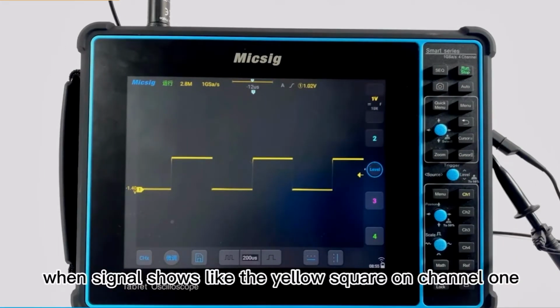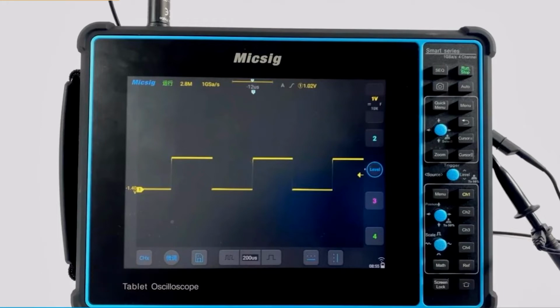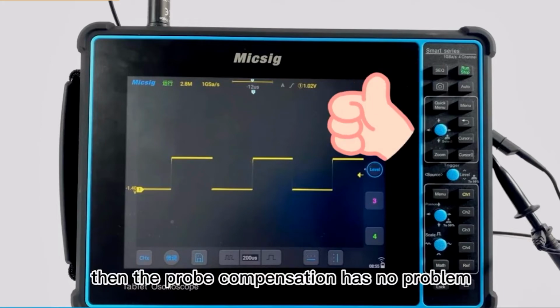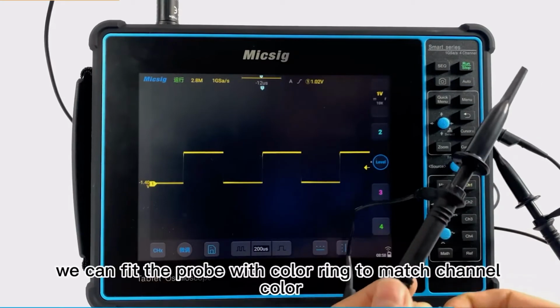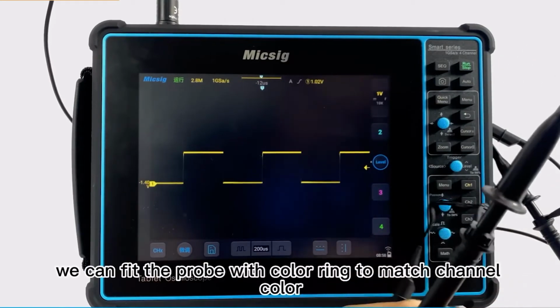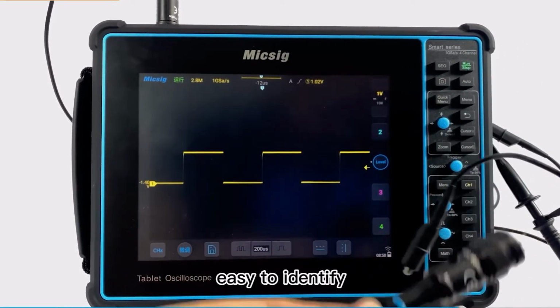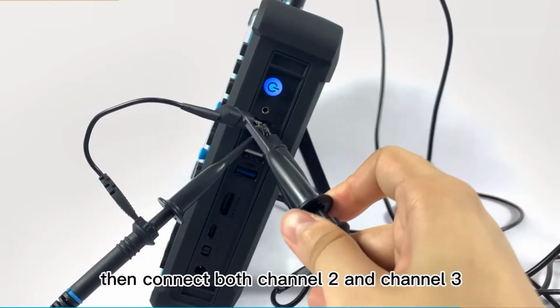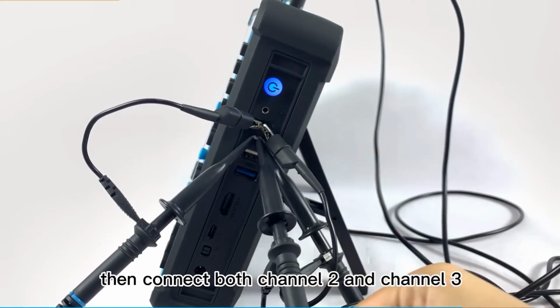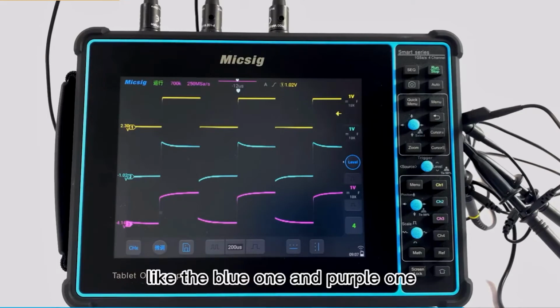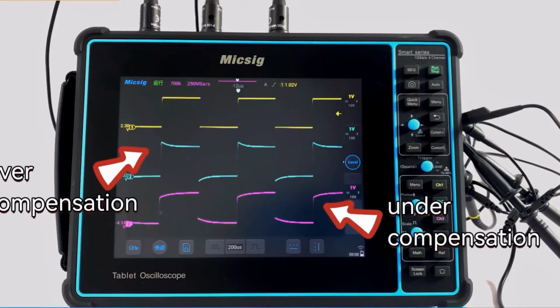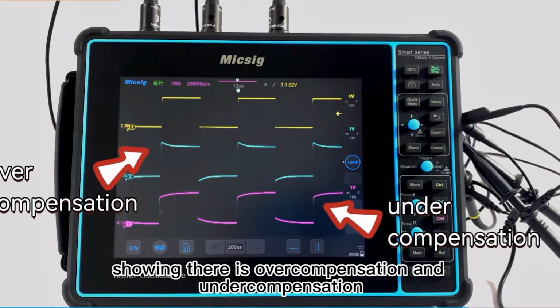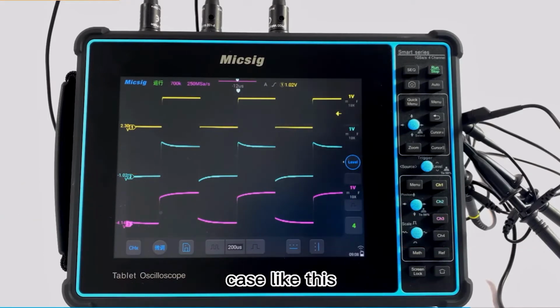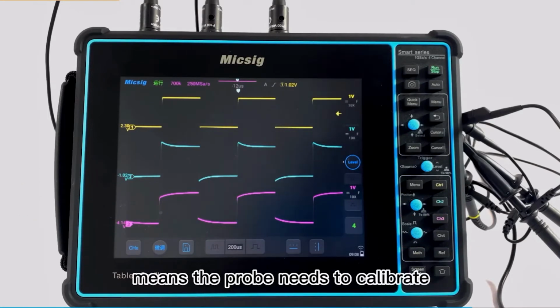When the signal shows like the yellow square on channel 1, then the probe compensation has no problem. We can fit the probe with a color ring to match the channel color, easy to identify. Then connect both channel 2 and channel 3. Like the blue one and purple one, showing there is overcompensation and undercompensation. A case like this means the probe needs to be calibrated.